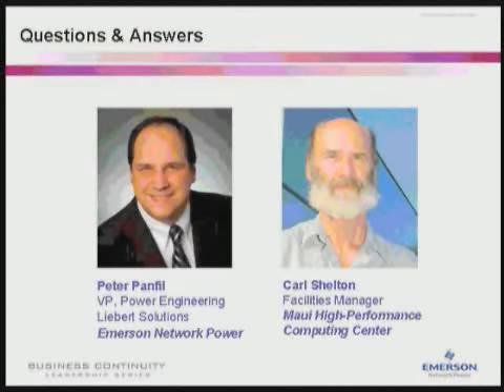And so it can deal very effectively and very efficiently with the heat that's being generated right there in that high-density rack. In that configuration, the base level cooling would cool, let's say, the lower portion of the rack, and as the cold air runs out, that supplemental cooling system would cool the top end of the rack and keep you from having vulnerable servers there in the rack.